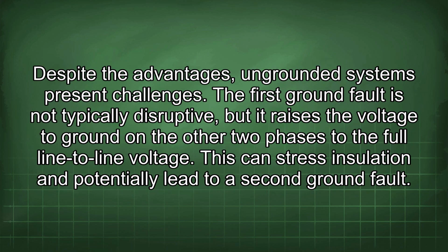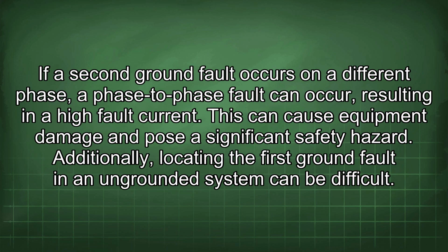Despite the advantages, ungrounded systems present challenges. The first ground fault is not typically disruptive, but it raises the voltage to ground on the other two phases to the full line-to-line voltage. This can stress insulation and potentially lead to a second ground fault. If a second ground fault occurs on a different phase, a phase-to-phase fault can occur, resulting in a high fault current. This can cause equipment damage and pose a significant safety hazard.